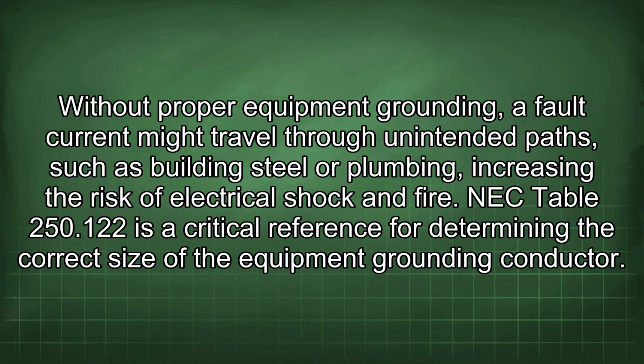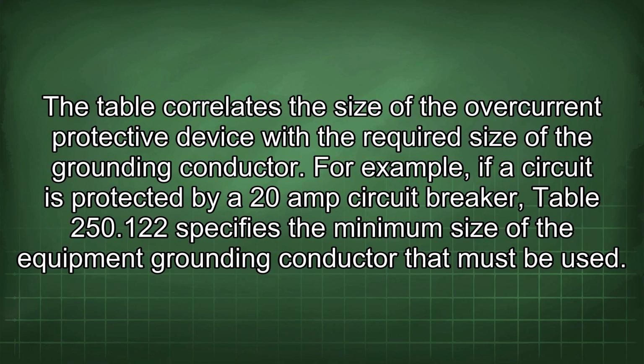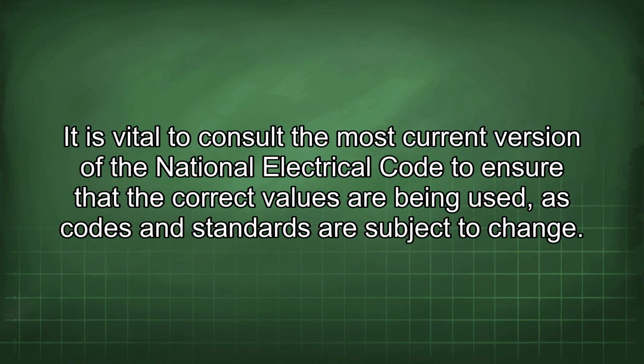NEC Table 250.122 is a critical reference for determining the correct size of the equipment grounding conductor. The table correlates the size of the overcurrent protective device with the required size of the grounding conductor. For example, if a circuit is protected by a 20 amp circuit breaker, Table 250.122 specifies the minimum size of the equipment grounding conductor that must be used. It is vital to consult the most current version of the National Electrical Code to ensure that the correct values are being used, as codes and standards are subject to change.